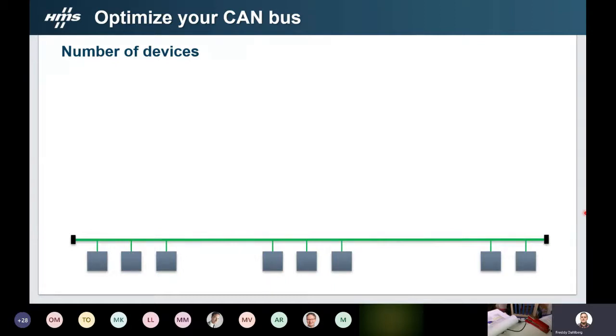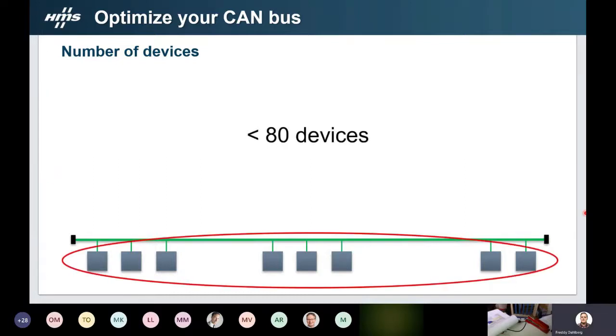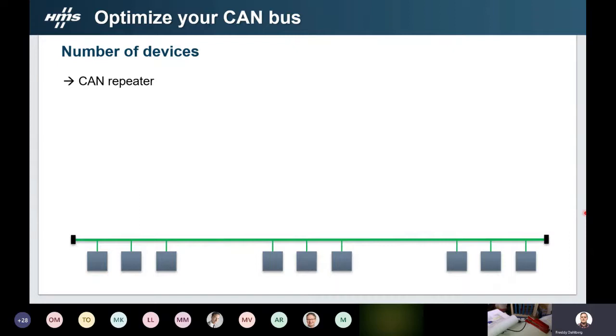So another challenge is the number of devices. What about if you have more than 80 devices? Then you might run into problems with the signals becoming too weak. This is because CAN transceivers do not have enough power to drive the voltage levels of so many devices. Again, a CAN repeater can be used, which then amplifies the signal.